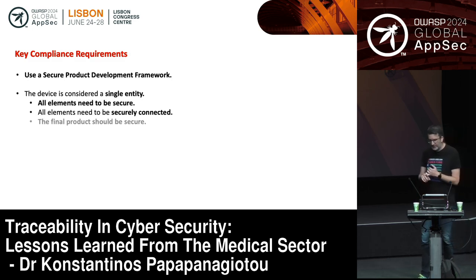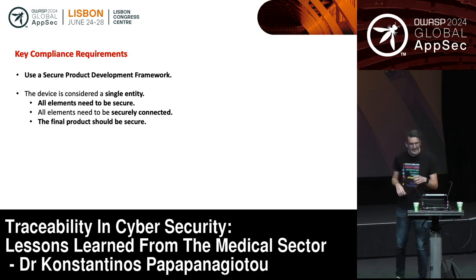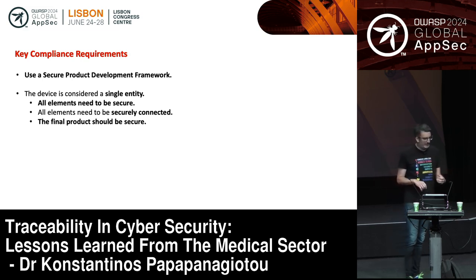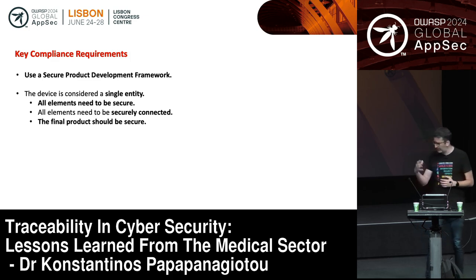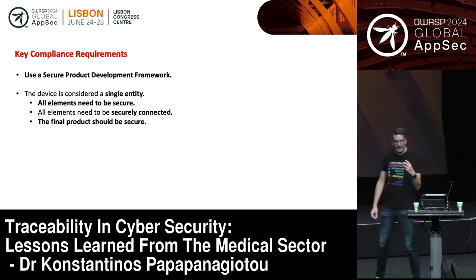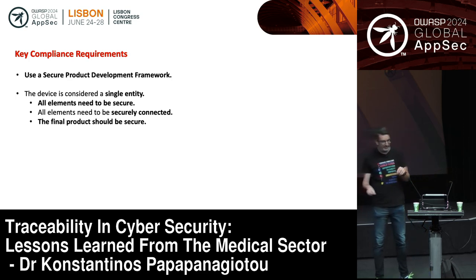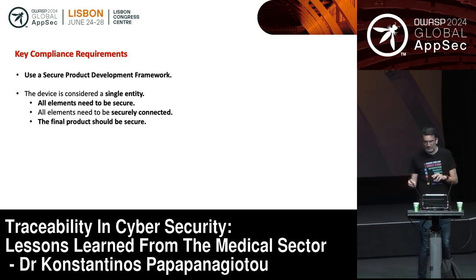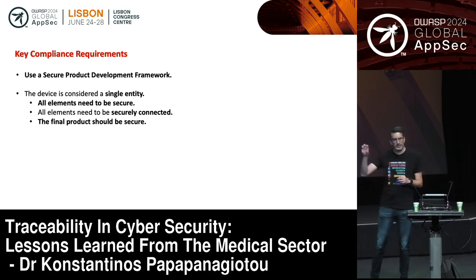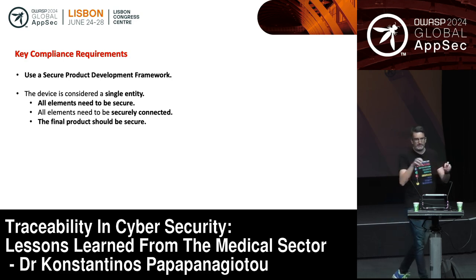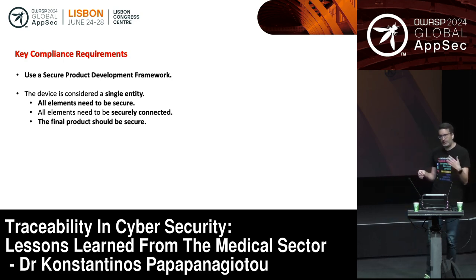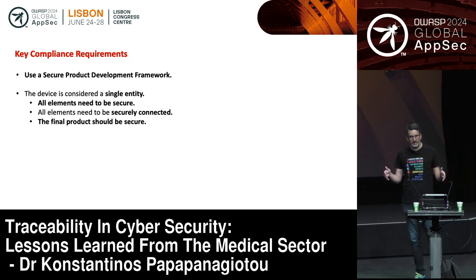Another requirement that comes up, though it's not explicitly defined, is that the medical device is considered a single entity. We don't have individual elements that work independently of each other. It might be composed of a Windows PC, an embedded device, and a catheter, but these are not three independent devices. FDA and the EU MDR view this as a single device and instruct you to treat it as such.